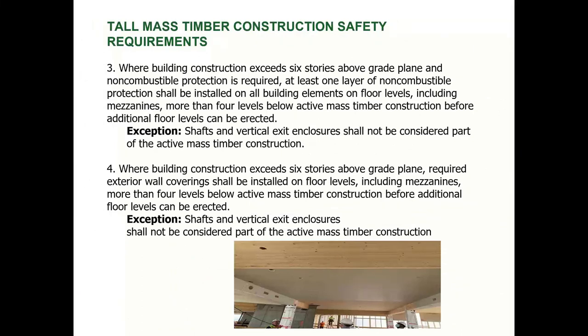Where the building exceeds six stories above grade plane, which applies to all tall mass timber buildings since it's not considered tall until it goes above six stories, you have to have non-combustible protection, at least one layer of type X 5/8 gypsum wallboard. This goes on the inside where required, which would be type 4A or 4B, and on the outside as the building goes up, within four stories of the lowest floor of active construction. So as the building goes up, the non-combustible protection goes up with it.